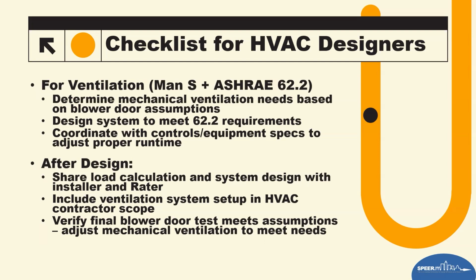So if they slack off just a little bit, or they get a new contractor and they're not doing the same thing as they did before, well, now instead of it being 4, we're at 4.8 and you're trying to get it tighter. If it's left that way because there's no way to fix it, because it's an envelope issue that's behind the cladding, brick, sheetrock, and it can't be fixed, or it's an encapsulated home with foam and you can't find the air leakage because of the way the framing is done, you can't get to it anymore. Now the sizing is incorrect and it needs to be addressed. Changing the speed of the equipment, maybe from a high speed to a medium speed, slows down airflow to offset the oversizing of the equipment.